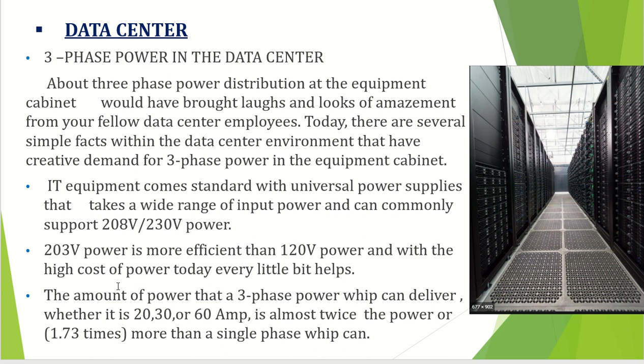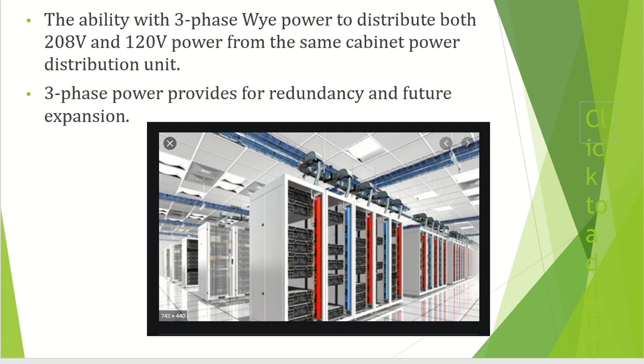208 volt power is more efficient than 120 volt power, and with the high cost of power today, every little bit helps. The amount of power that a three-phase power whip can deliver, whether it is 20, 30 or 60 amperes, is almost twice the power, or 1.73 times more than a single-phase whip can. We will see data centers having three-phase supply like this. The ability with three-phase power to distribute both 208 volt and 120 volt power from the same cabinet power distribution unit. Three-phase power provides for redundancy and future expansion. Thank you.